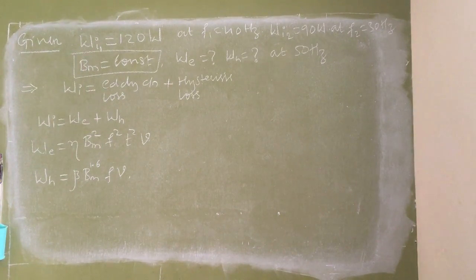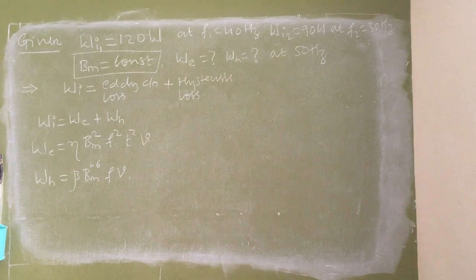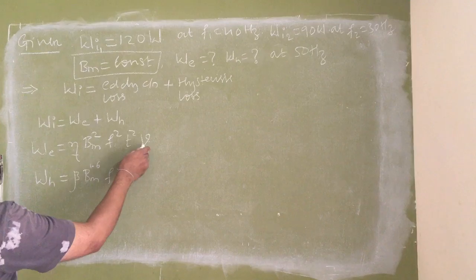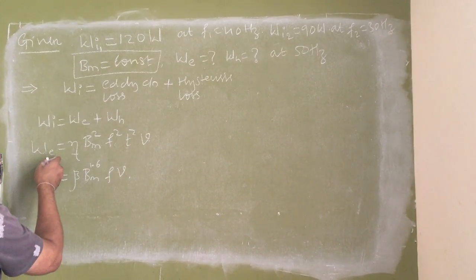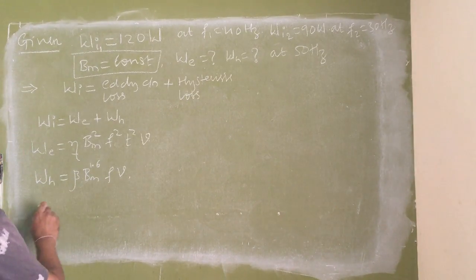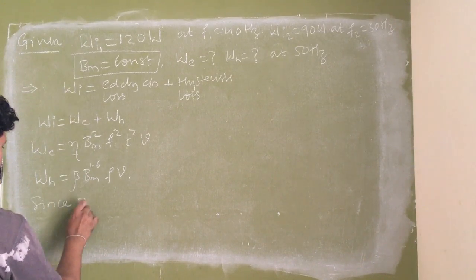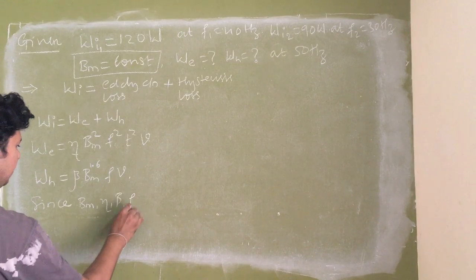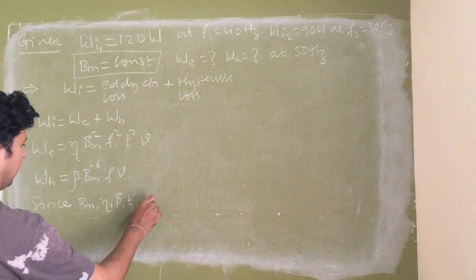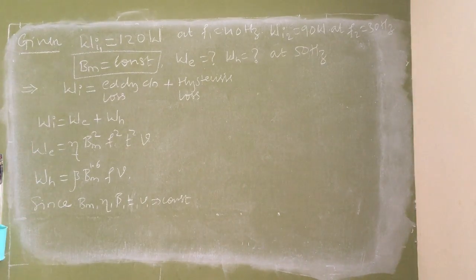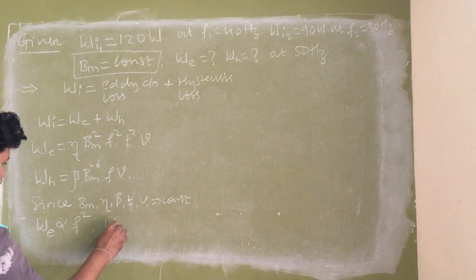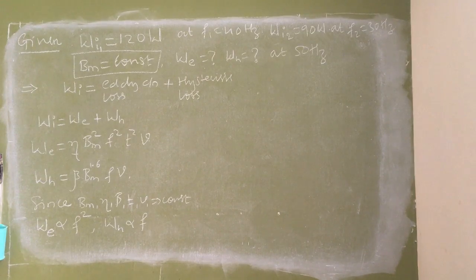But it is mentioned that for all the variation in the frequency, my flux density is kept constant. Therefore Bm square and Bm to the power 1.6 are also constants for me. So eta is a constant, T and V are constant, and Bm is also kept constant. Therefore eddy current loss is proportional to frequency square, and hysteresis loss is proportional to frequency.